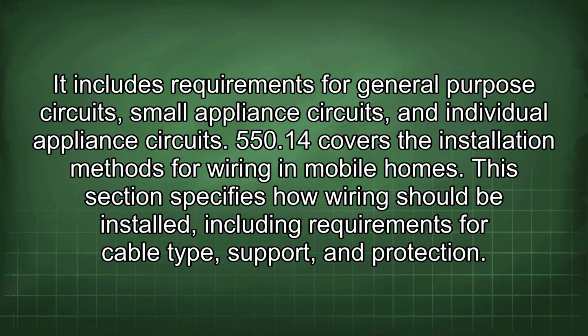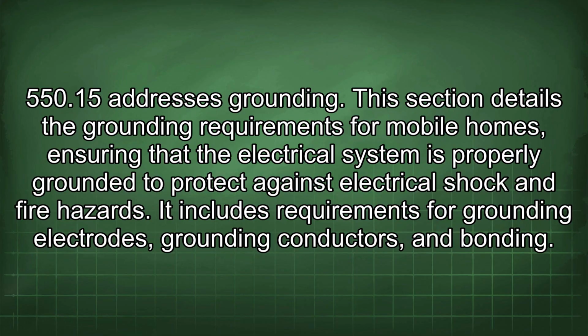550.14 covers the installation methods for wiring in mobile homes. This section specifies how wiring should be installed, including requirements for cable type, support, and protection. 550.15 addresses grounding. This section details the grounding requirements for mobile homes, ensuring that the electrical system is properly grounded to protect against electrical shock and fire hazards. It includes requirements for grounding electrodes, grounding conductors, and bonding.